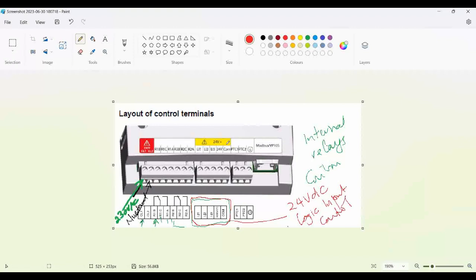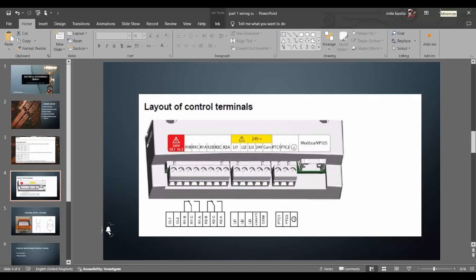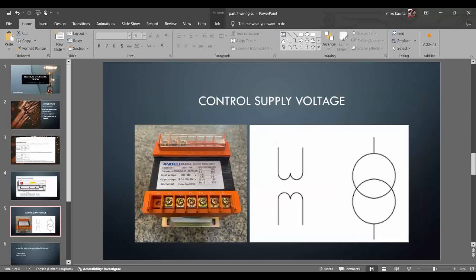The turn-on/off time delay includes hardware delay of less than 15 milliseconds and software delay of 70 to 85 milliseconds, anti-bounce. The third connector includes the PTC, which is responsible for motor overheat protection. The PTC probe connection, labeled PTC1 and PTC2, has a total resistance of 750 ohms at 25 degrees Celsius, 77 degrees Fahrenheit. The step-down transformer is represented with any of these symbols, as we shall see further in the video.